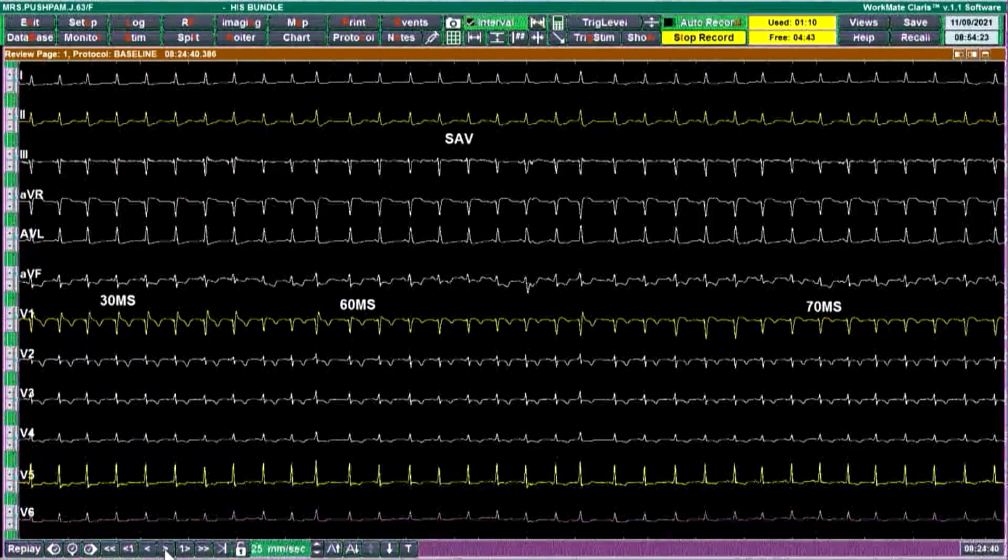So if you are going to capture the anode also, meaning that simultaneously you are capturing the right side of the septum and the left side of the septum, that means that there will be a simultaneous activation of the septum, so you will not have any RBBB delay. So we have demonstrated the anodal capture also. Can you show, William, the anodal capture threshold?